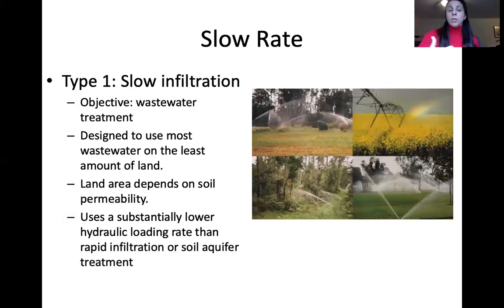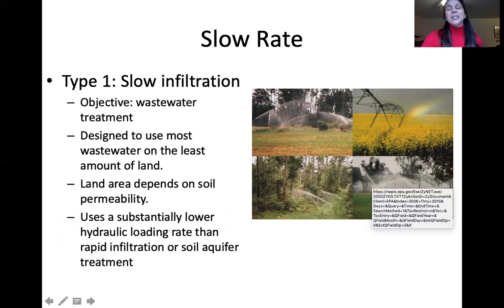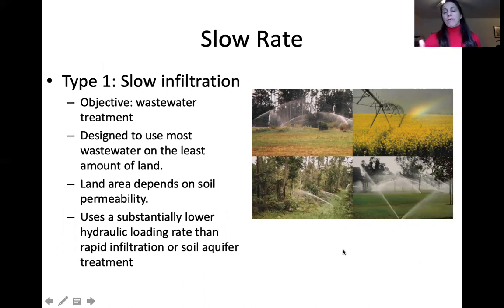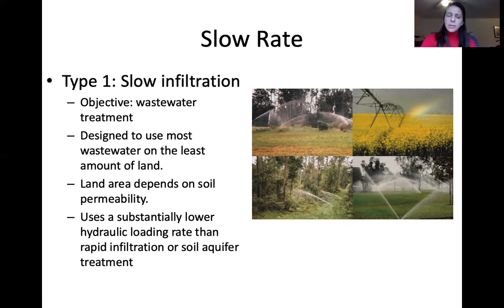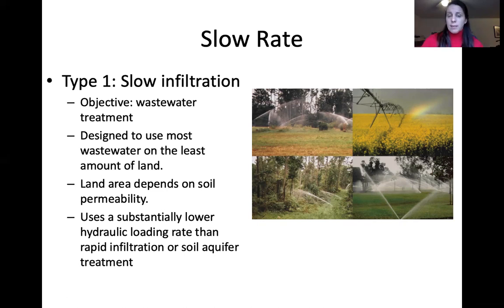Type one is slow infiltration — wastewater applied via sprinklers into forested areas or croplands. The objective for forest areas is to use the most wastewater on the least amount of land. Land area needed is 100% based on soil permeability and evaporation. It uses a lower hydraulic loading rate than rapid infiltration or soil aquifer treatment, because everything must infiltrate within the landscape it's applied to.